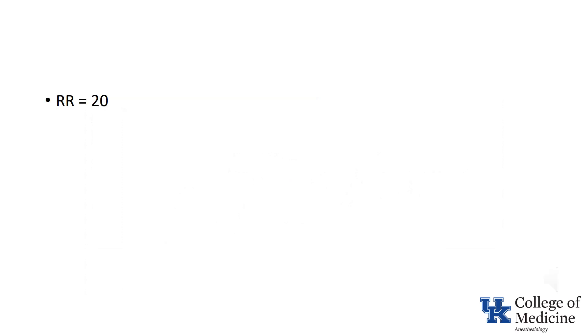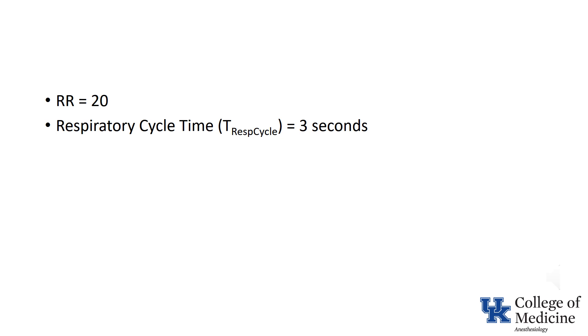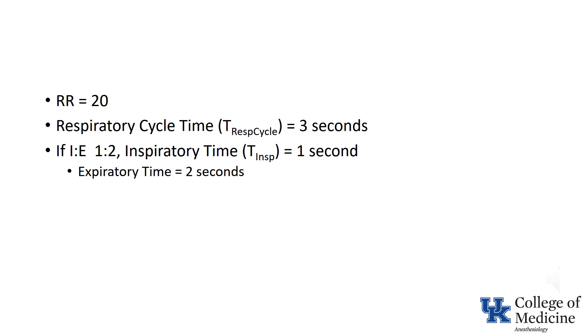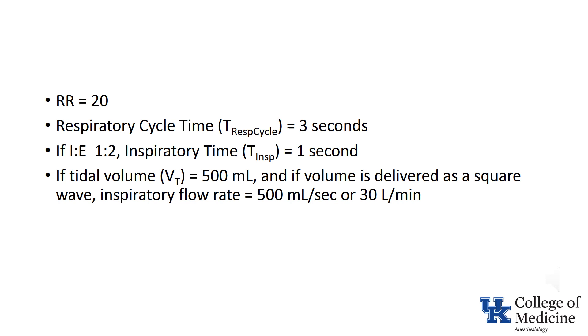Here are some sample calculations. Start with a respiratory rate of 20 breaths per minute — that means the respiratory cycle time is 3 seconds. With a normal I:E ratio of 1:2, the inspiratory time is 1 second and the expiratory time is 2 seconds. With a tidal volume of 500 mL delivered in 1 second as a square wave at a constant inspiratory flow rate, the inspiratory flow rate is 500 mL per second, or 30 liters per minute.